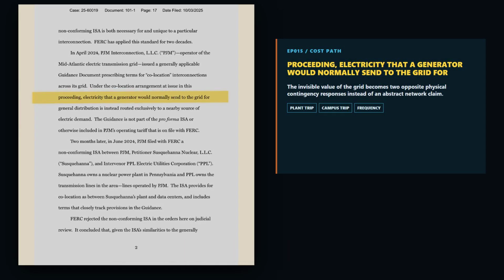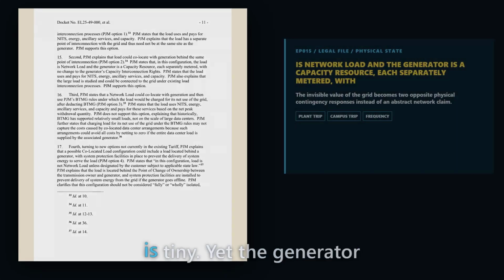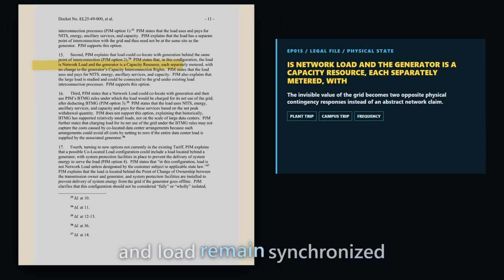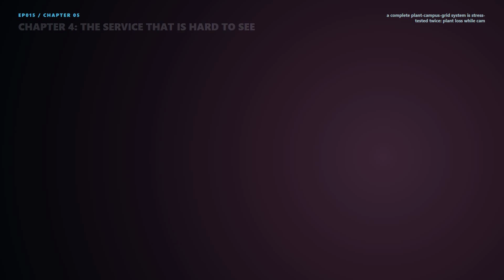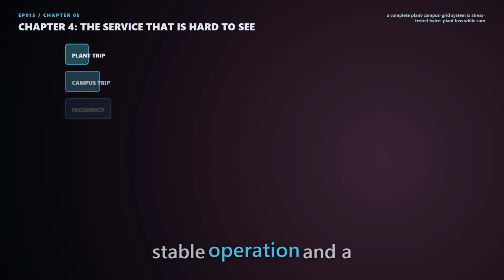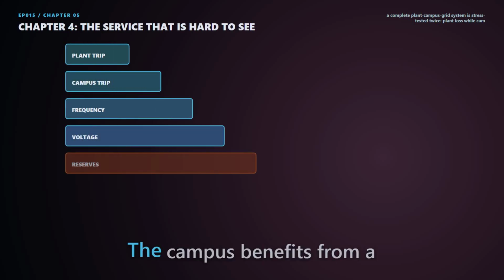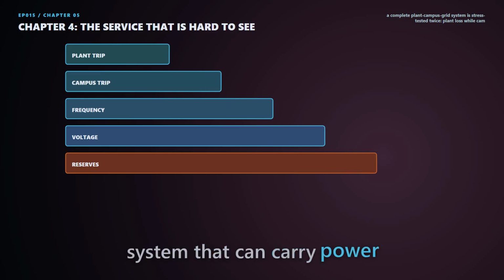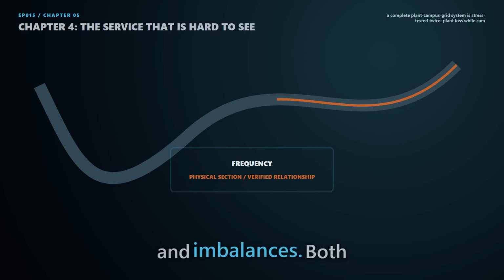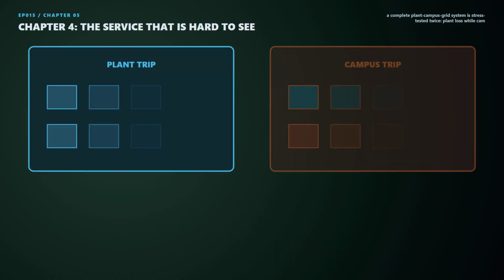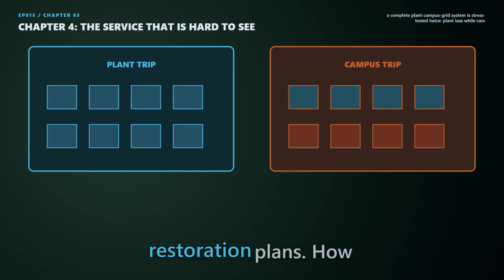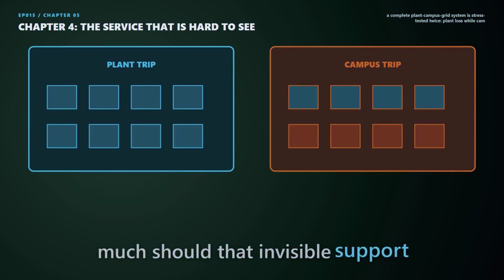Suppose a data center normally takes nearly all of its power from the adjacent generator. Its metered network withdrawal is tiny, yet the generator and load remain synchronized through PJM. The plant relies on the grid for stable operation and a market for excess output. The campus benefits from a system that can carry power during maintenance, faults, and imbalances. Both benefit from regional operators, protection coordination, and restoration plans. How much should that invisible support cost?